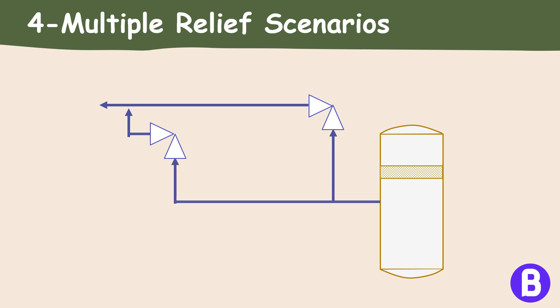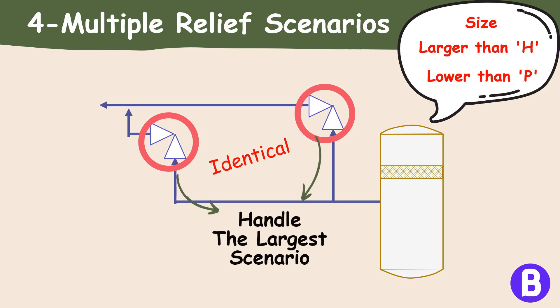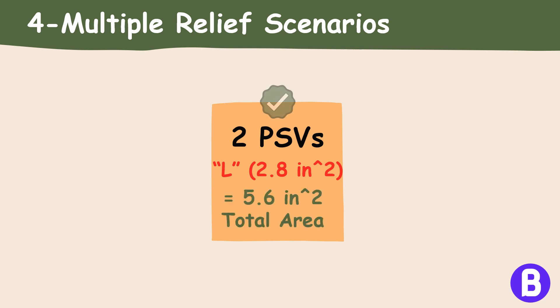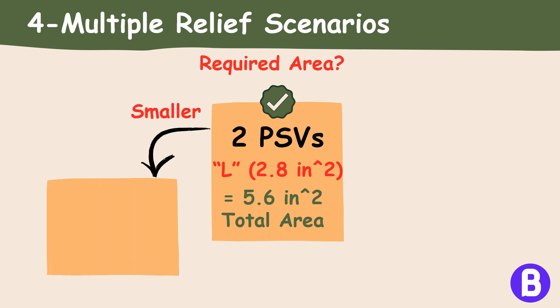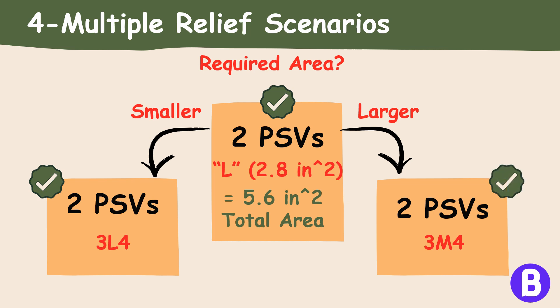Alternatively, another solution is to choose two identical PSVs of identical size — larger than H but smaller than P — so that the sum of both orifice areas handles the largest scenario. For example, two PSVs with orifice L (2.8 in² each) would yield a total area of 5.6 in². If the required area is less than 5.6 in², two PSVs of size 3L4 can be chosen; if a larger area is needed, two PSVs of size 3M4 can be selected.